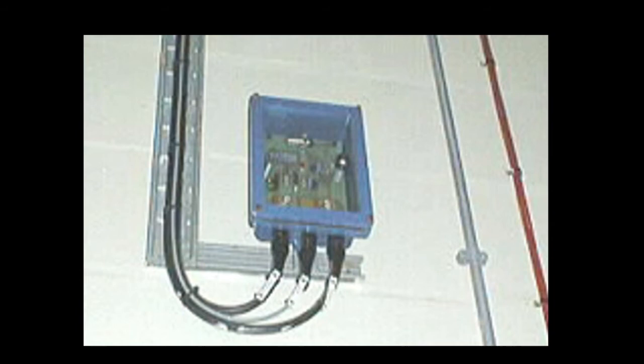Aside from the economic impact of halting operations for a faulty CAAS alarm, stopping operations quickly for an evacuation can actually be very dangerous. Not only are workers handling fissile materials, but they may also be handling volatile chemical compounds. Workers are going to want to evacuate as quickly as humanly possible when the CAAS alarms sound, and a worker could easily violate an administrative limit or spill a dangerous chemical during the rush to evacuate. Therefore, requiring at least 2 out of 3 of the CAAS detectors to agree that a dangerous condition exists will reduce the likelihood of erroneous evacuations.